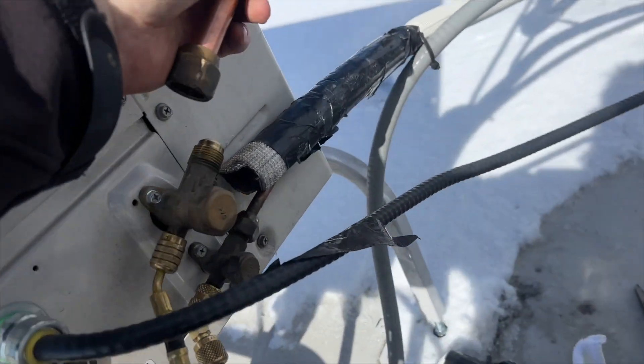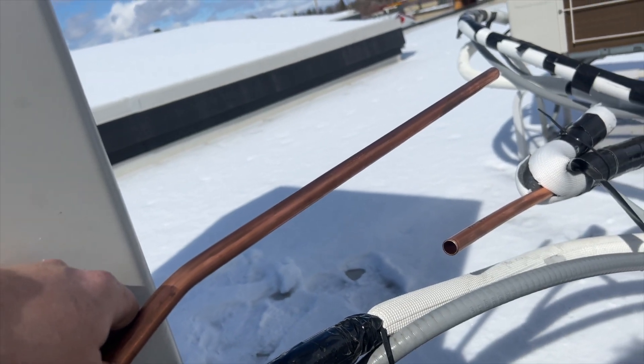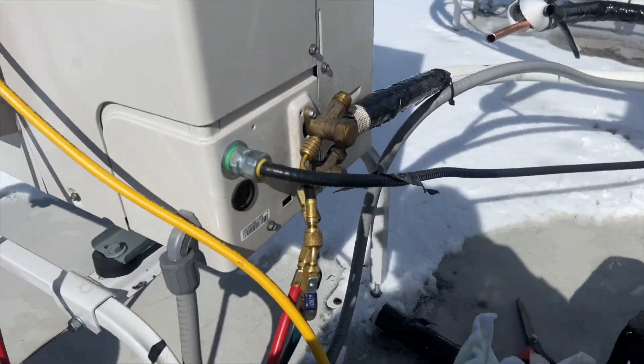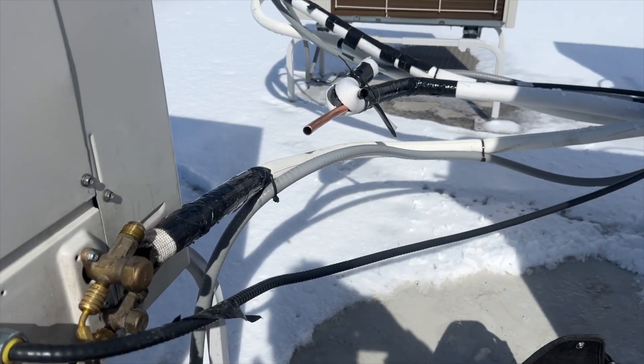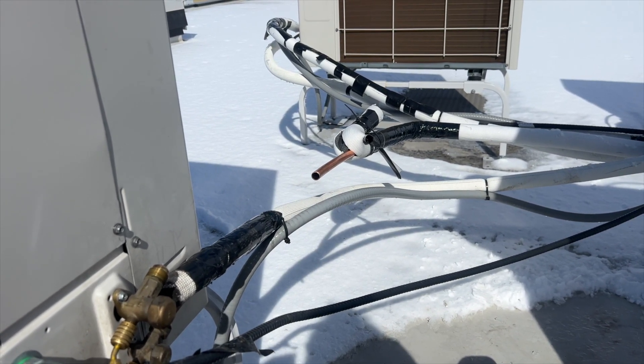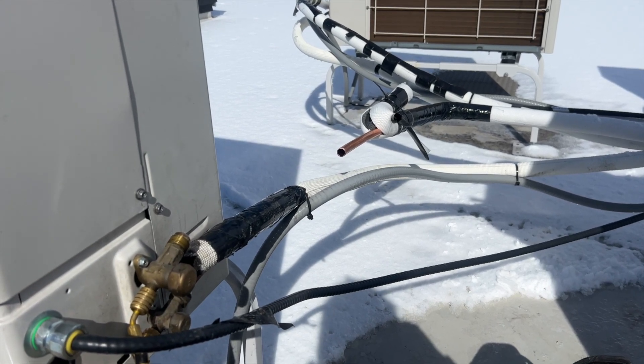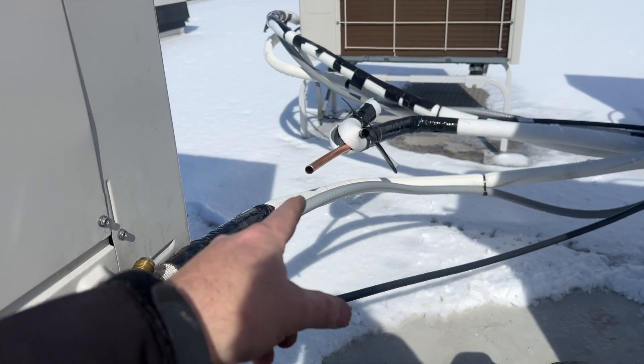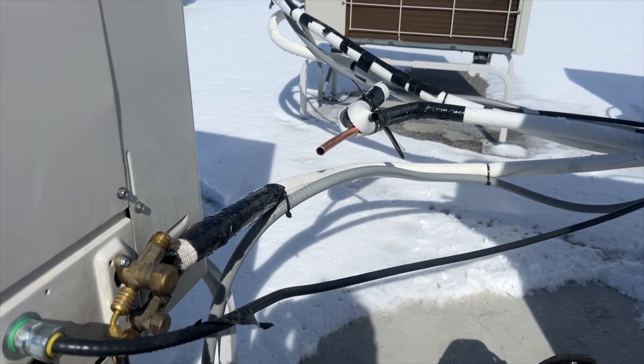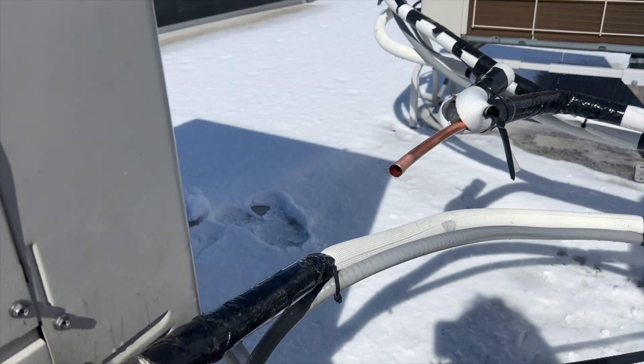I already got my nut on so I won't forget it. It's pretty much lined up and I have some wiggle room. I'm going to swage that piece so I can have one continuous new piece with only one braze point — trying to minimize the brazing as much as possible. I know it's a bit unconventional, but there's really no other option here. I could do two flares with a joining fitting, but I don't want to add another potential leak point.